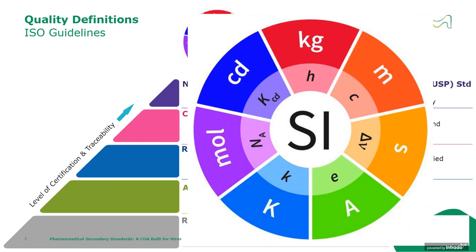Metrological traceability means that measurements can be meaningfully compared across different places, at different times, by different people, and using different equipment, because we set a standard of ground zero where to measure from. The measurement result is related back to a reference through a documented and unbroken chain of calibrations tracing back to the SI unit of measurement.